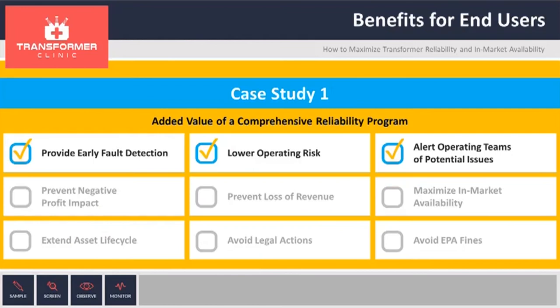Some of the benefits for the end user here were early detection — even when the DGA gassing trend was low, we were still able to pinpoint the location of the source. Once they knew there was a problem on that unit, they actually prevented anybody from getting close to the transformer, therefore increasing safety for the personnel. And they had a plan in place in case there was a failure on the unit.